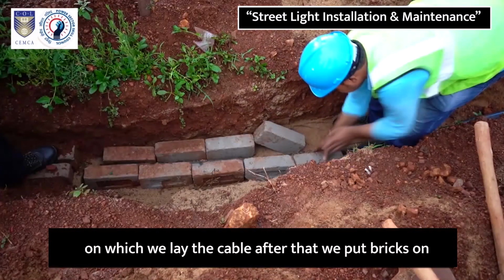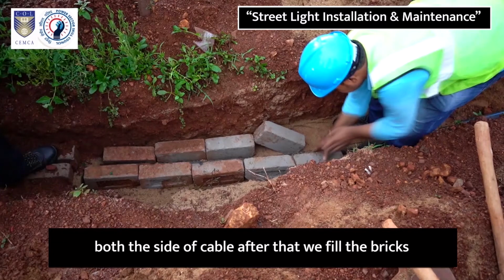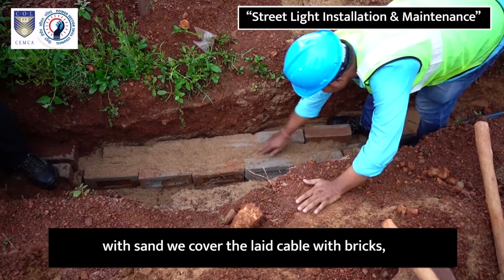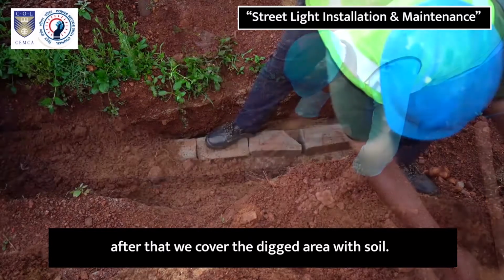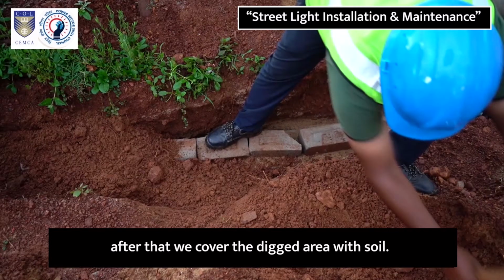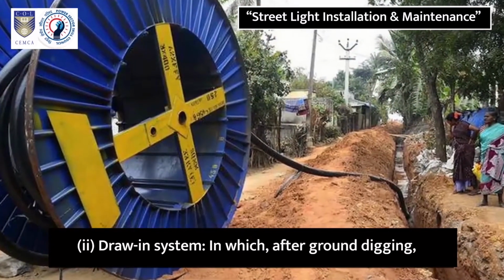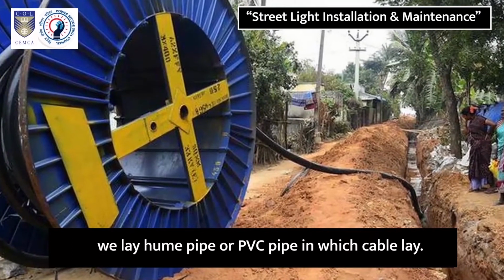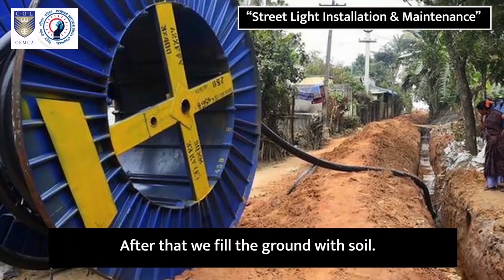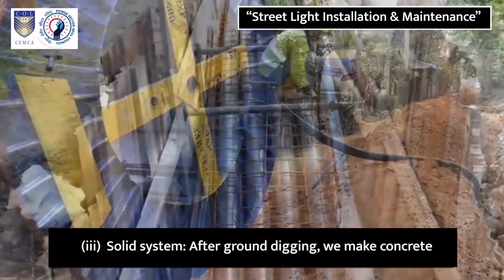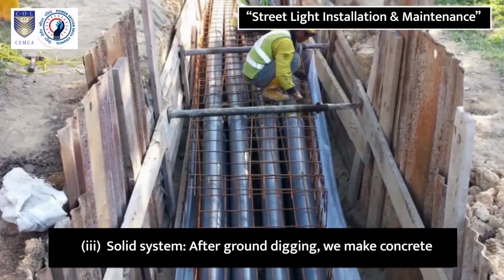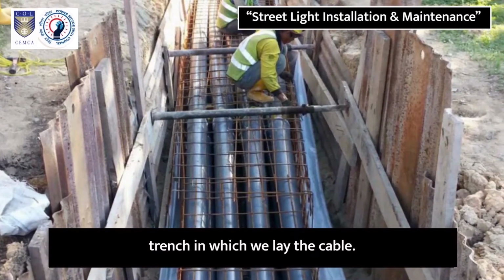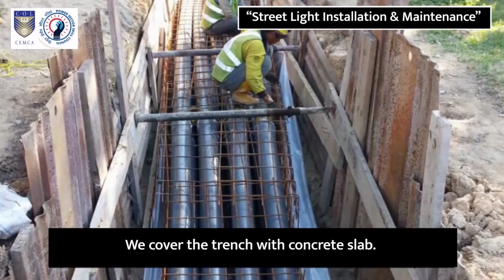After that we put bricks on both the sides of the cable. After that we fill the bricks with sand. We cover the laid cable with bricks. After that we cover the dug area with soil. 2. Draw-in system, in which after ground digging we lay hume pipe or PVC pipe in which the cable is laid. After that we fill the ground with soil. 3. Solid system. After ground digging we make a concrete trench in which we lay the cable. We cover the trench with concrete slab.